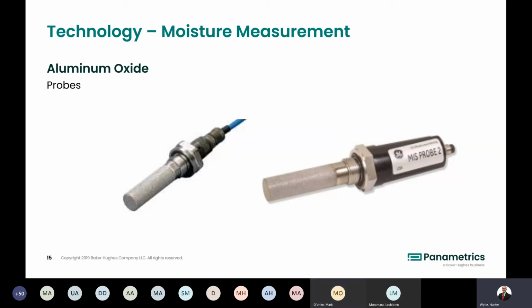Certainly, and that's exactly it. Each process, and I believe that this was mentioned earlier as well, does have certain recalibration times just based on how wet it is. It all is about inherently how much moisture continues to remain adsorbed onto the probes as well. So they'll continue to drift and read slightly higher or slightly drier over time. So it really comes down to being able to know exactly what your process is and working with your local application teams to be able to determine what the best timing is for those programs as well. Yeah.